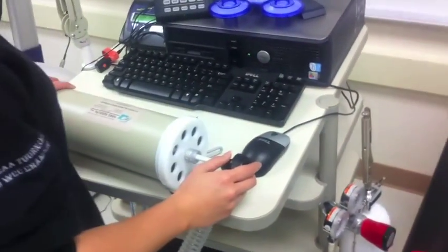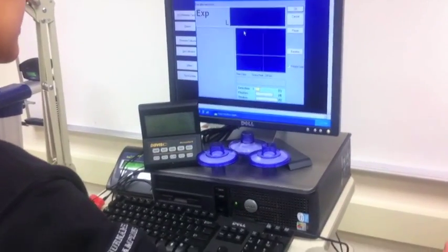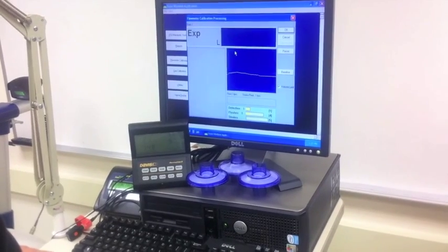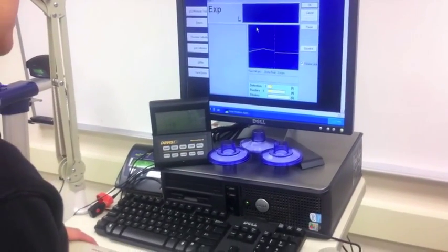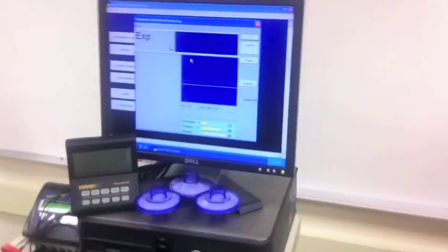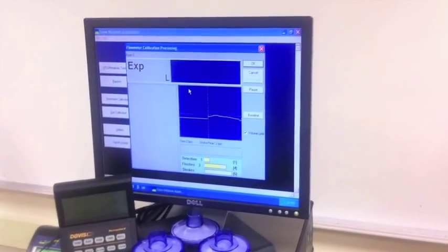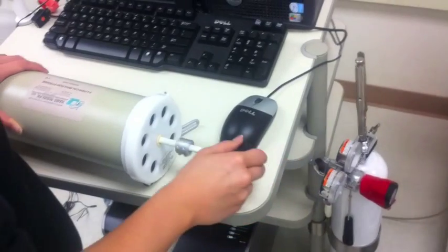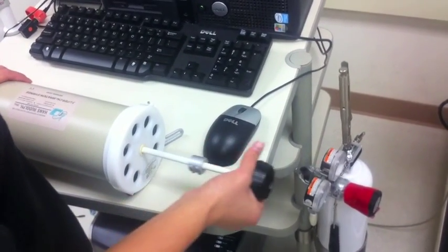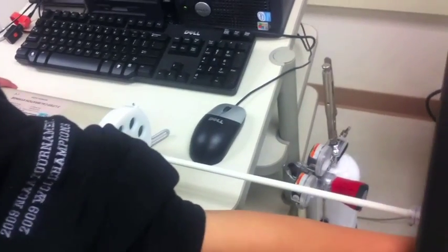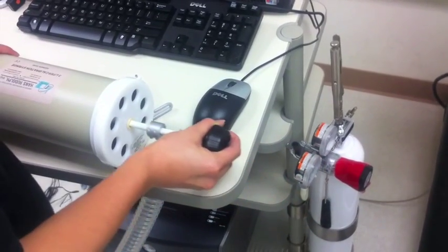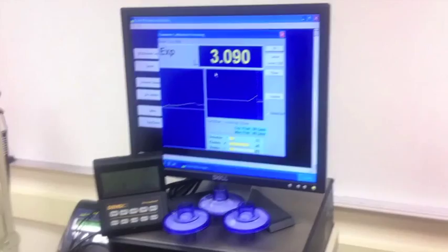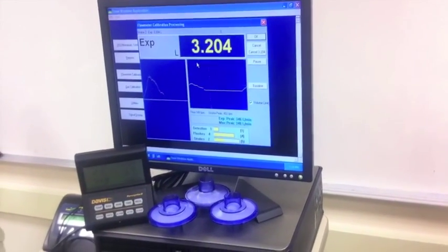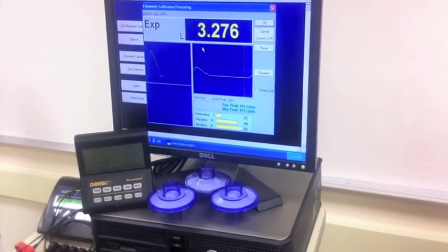You begin by slowly flushing the cylinder and following the instruction at the bottom of the screen. It will tell you how many flushes you've done and how many there are left. Once you get to the stroke column, you will begin pushing slowly and gradually getting faster within 5 strokes. And that is the end of the flow meter calibration.